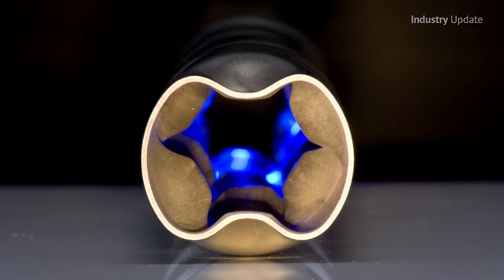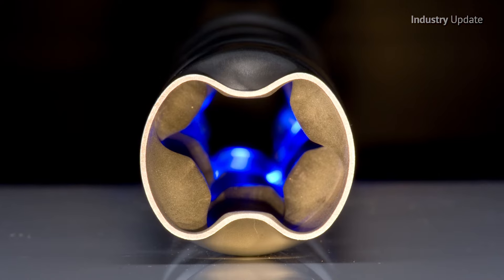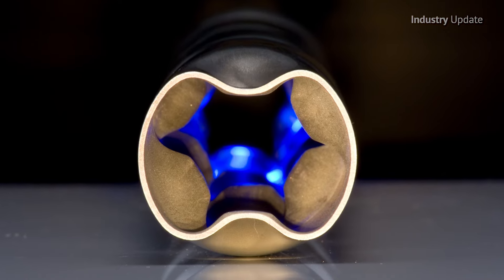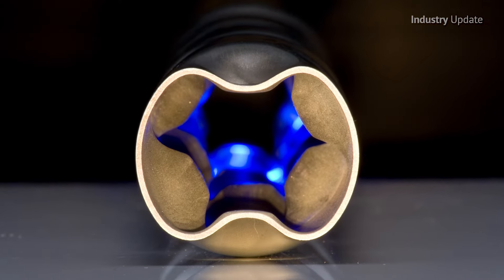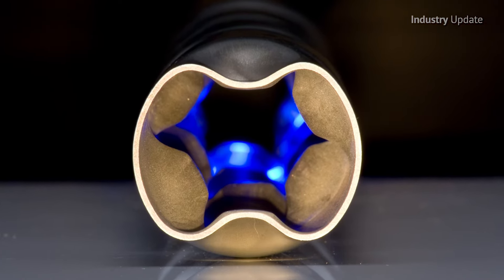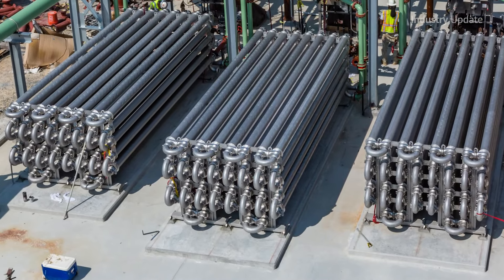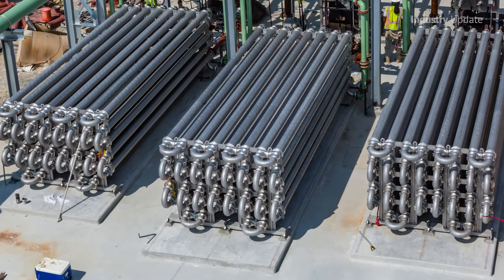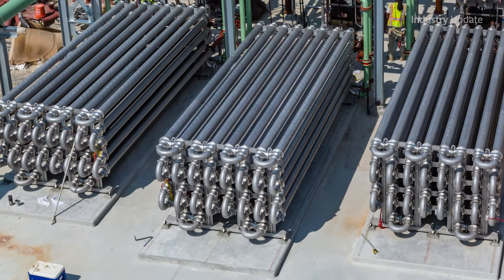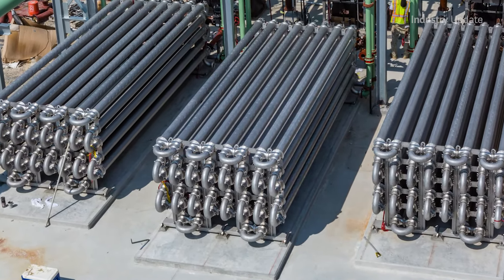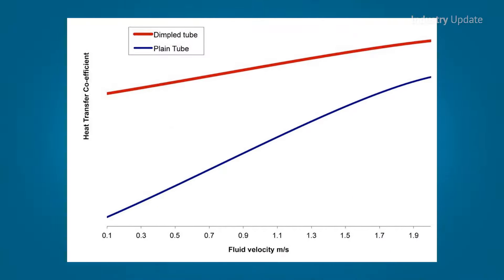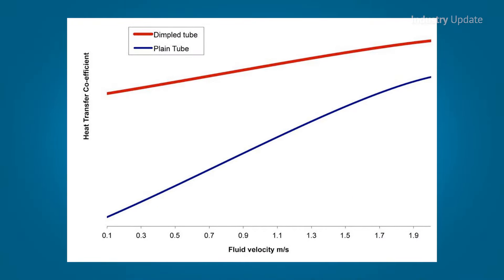By arranging dimples at the right pitch and centers, the liquid is jostled but not restricted, though there's little change in the pressure drop characteristics compared to plain, undimpled surfaces. However, there is a significant change in the heat transfer rates.